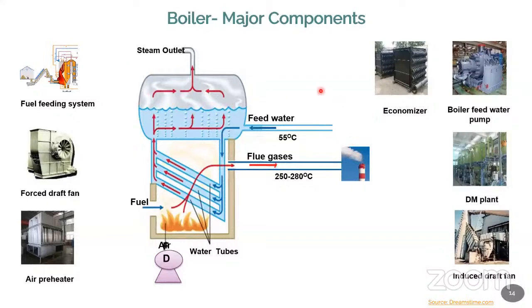Now you will mix up the 70 degree condensate water. So what will happen? The temperature of the feed water tank will improve. Correct? Temperature of the feed water tank improves. So assuming that it's 35 degrees earlier, now you mix up a huge quantity of 70 degree condensate water. Then it may increase to 55 degrees, or 60 degrees, or 70 degrees, whatever it may.